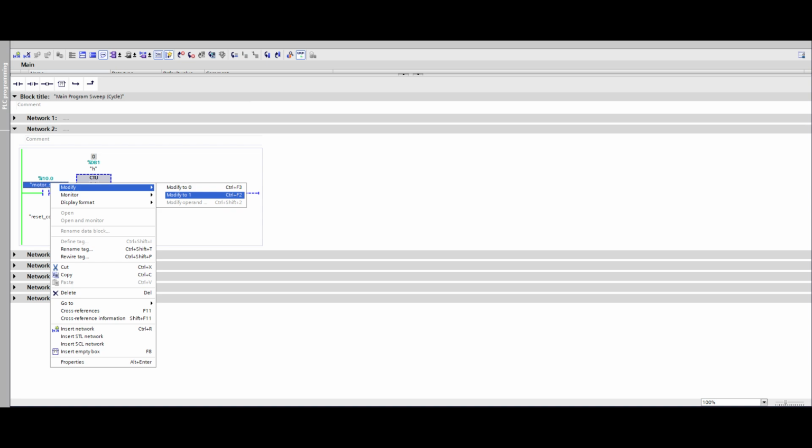Now, if the sensor sends a very short pulse, or if you are trying to change I0.0, which is the input, using a modify, that change might only exist for a fraction of the cycle, too short for the program to catch it. That's why TIA Portal may say successfully modified, but in your logic, nothing happens.